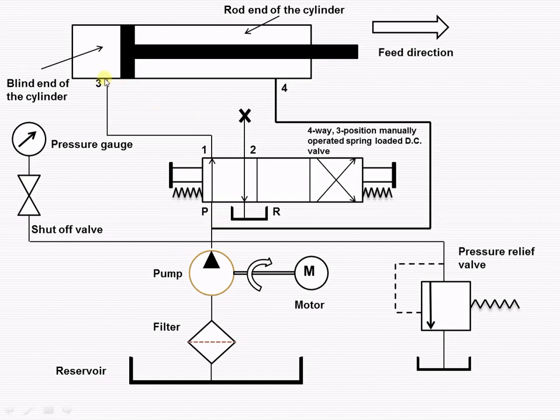The volume of fluid supplied to the blind end of the cylinder is greater than the pump flow rate, and therefore the speed of extension of the piston is greater than the retraction speed. This is known as regeneration. In this way, the regenerative circuit is used for increasing the speed of the piston in the forward or feed direction.